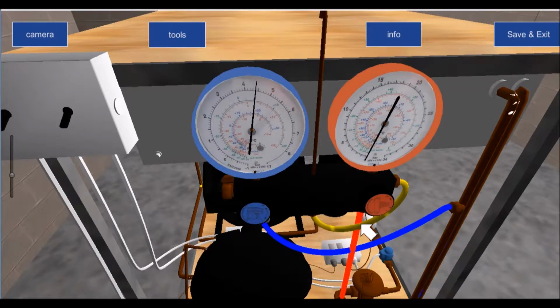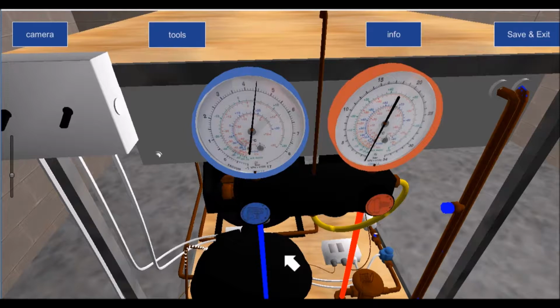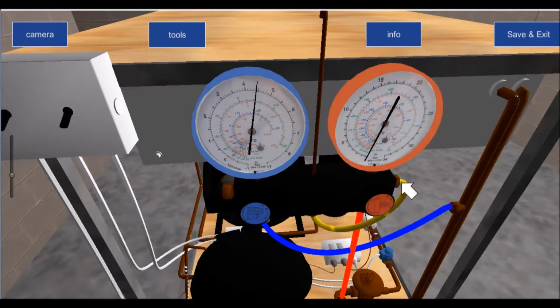So one of the other things that you'll notice, this service line, what I've done with this service line is I've actually blanked it off. So rather than leaving it dangling, sitting down like we have these two red ones here, I get the yellow and I blank it. I fit a blank onto it, or I put it onto a blank connection on the actual manifold itself.